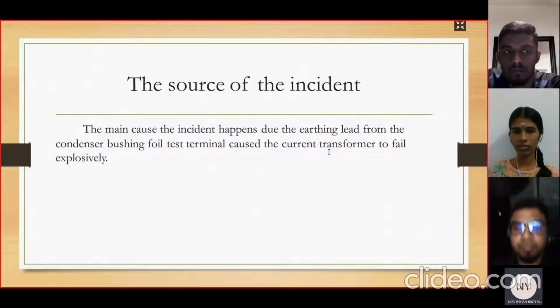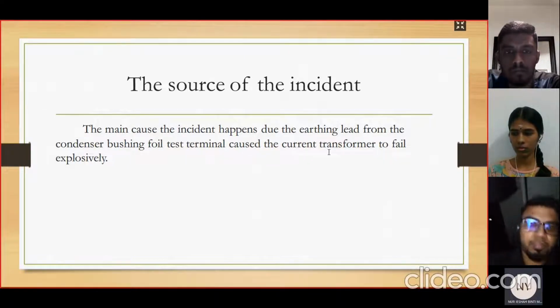The source of the incident. The main cause of the incident is that the earthing lead from the condenser bushing foil test terminal caused the current transformer to fail explosively.